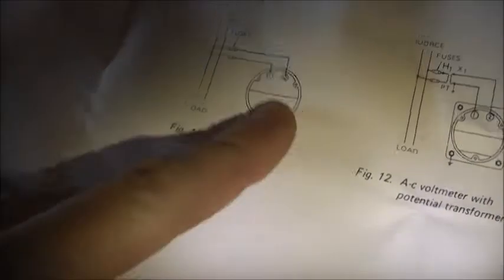Okay, this is how I would connect it. Source and load. So we got line coming into the power point, neutral coming into the power point. Now I'll measure the volts. It's quite simple, this does not have a potential transformer. It says here, when a circuit exceeds 600 volts, a potential transformer of the ratio and frequency rating indicated on the instrument nameplate must be used. This doesn't have a potential transformer, it's just a self-contained voltmeter, so I can just wire this straight up as per this diagram and it'll work.